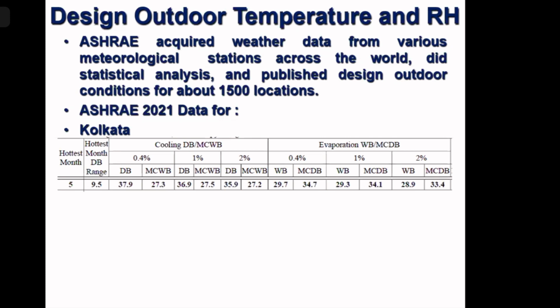Similarly, if we consider 1% occurrence level, the dry bulb temperature is 36.9, 1 degree centigrade less. That means if we consider 36.9 degrees centigrade as the design outdoor dry bulb temperature for a Kolkata air conditioning system, then 1% of the time over the reasonable life cycle of the AC plant, the outdoor temperature will be more than 36.9. And at 2% occurrence level, it is 35.9. For comfort air conditioning, we normally consider 36.9.